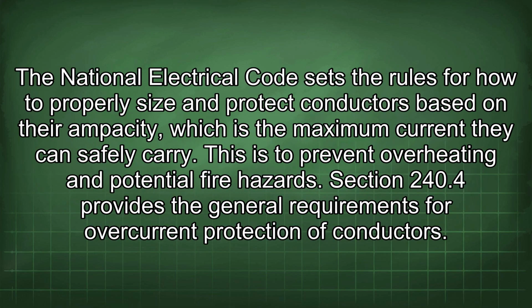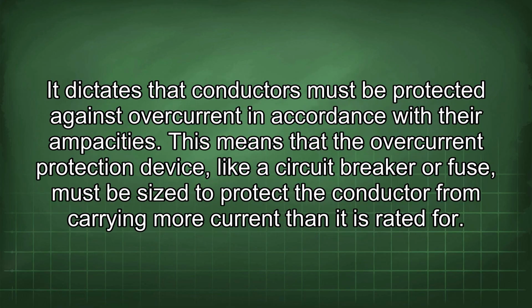The National Electrical Code sets the rules for how to properly size and protect conductors based on their ampacity, which is the maximum current they can safely carry. This is to prevent overheating and potential fire hazards. Section 240.4 provides the general requirements for overcurrent protection of conductors. It dictates that conductors must be protected against overcurrent in accordance with their ampacities. This means that the overcurrent protection device, like a circuit breaker or fuse, must be sized to protect the conductor from carrying more current than it is rated for.